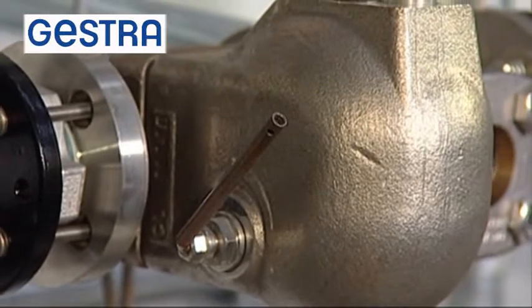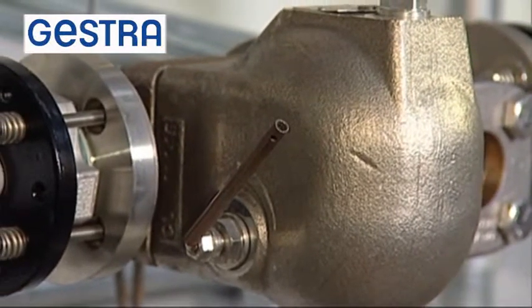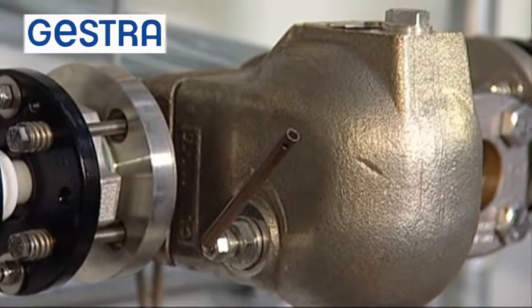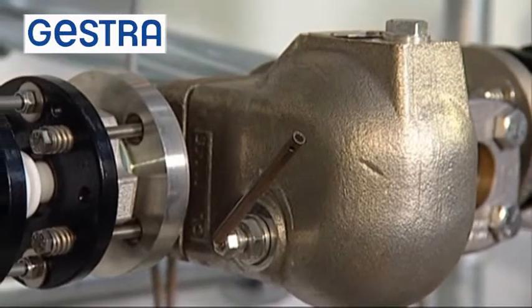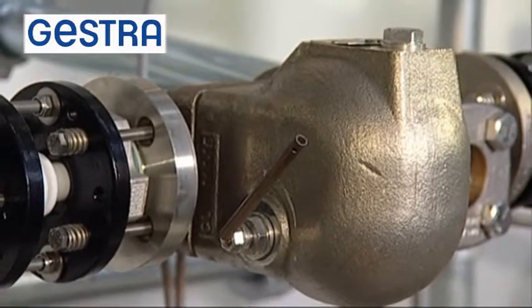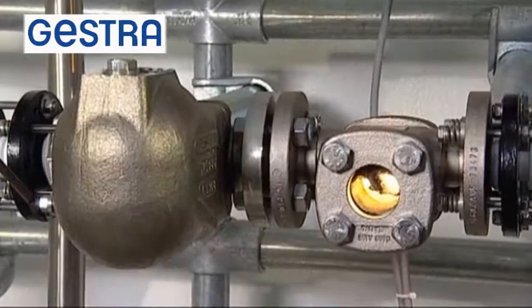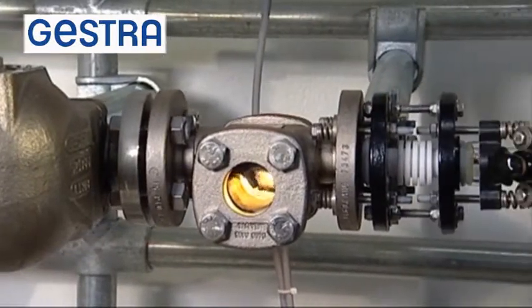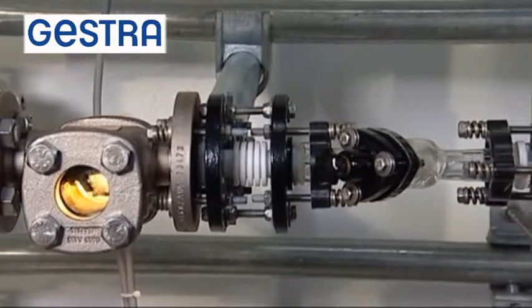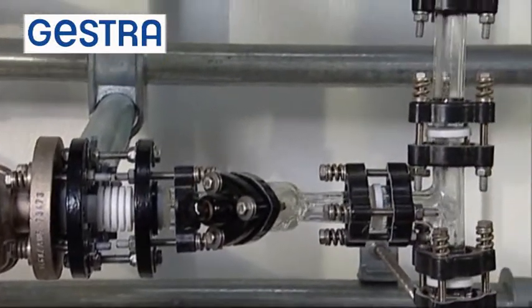This offers the possibility of achieving a forced opening of the unit. This may be necessary in practice whenever dirt increasingly accumulates in the steam traps as a result of increased corrosion in the system. In comparison to thermostatic steam traps, ball float traps offer special benefits.